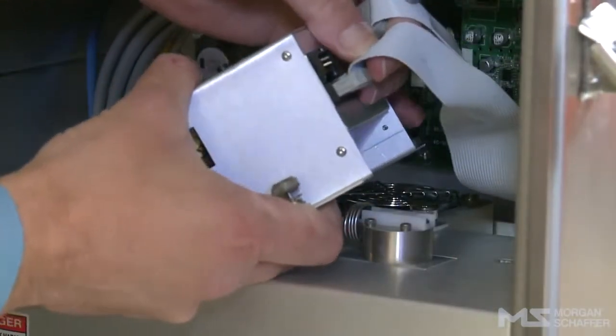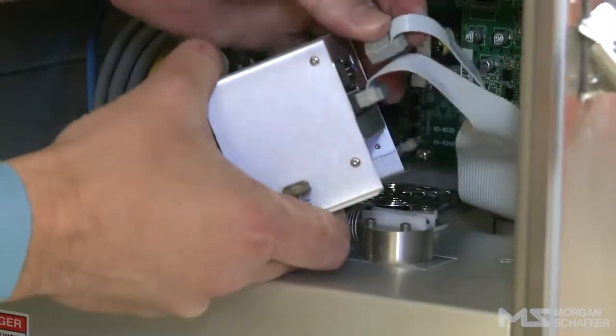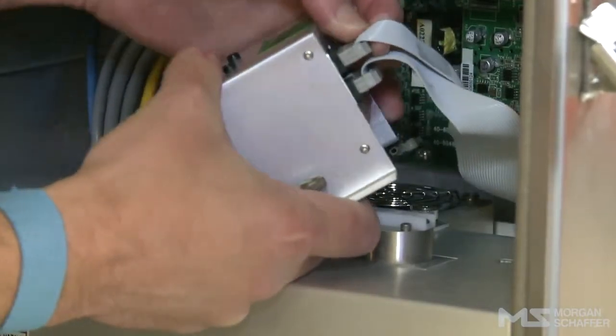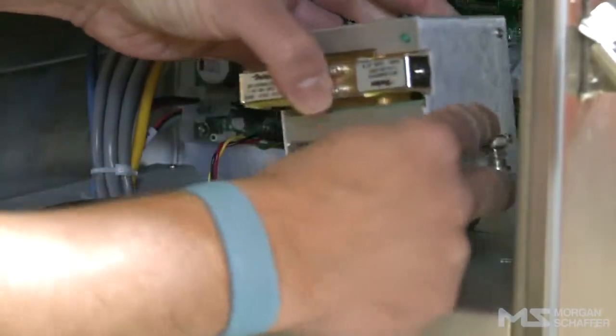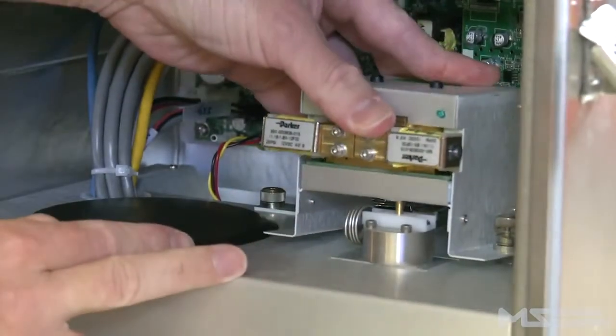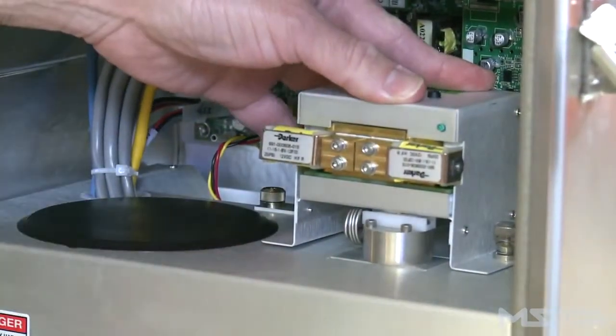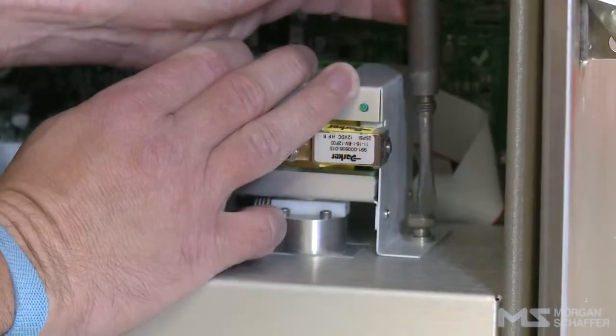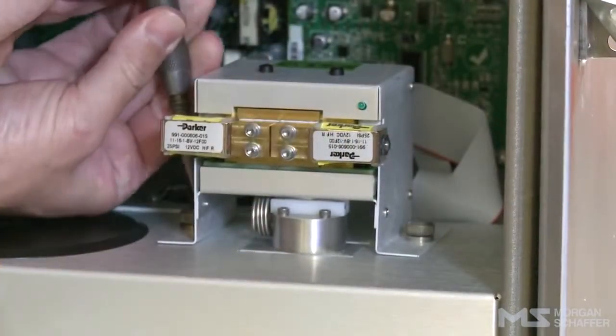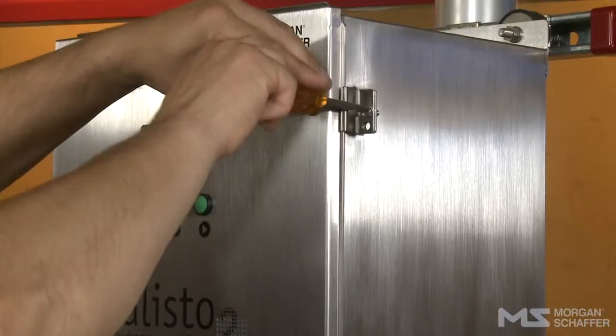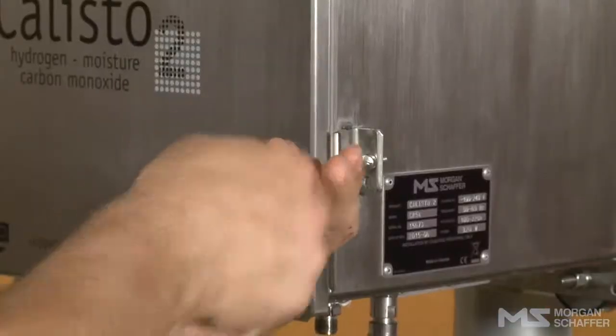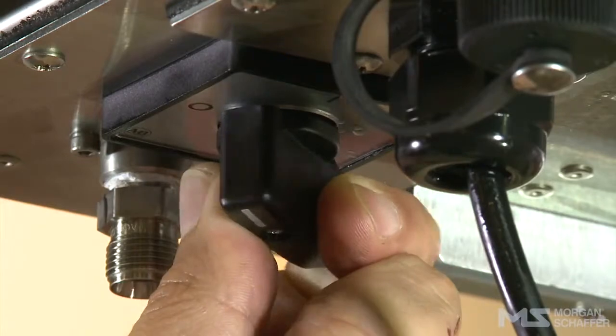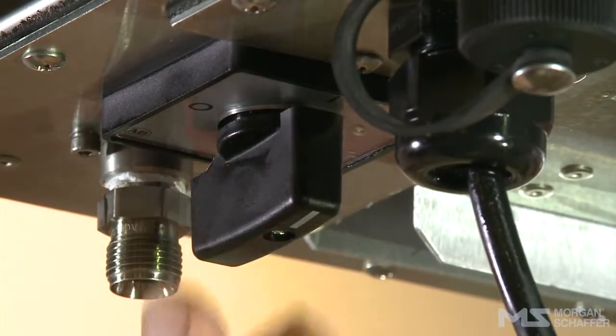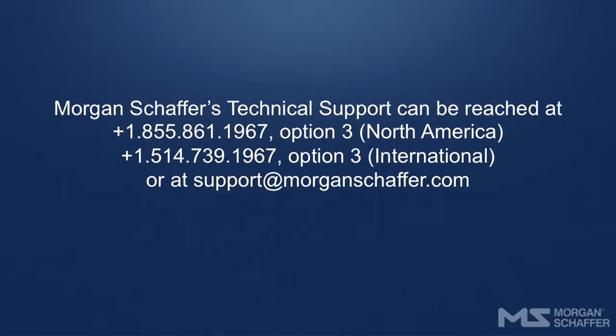Dispose of the old cell and prepare the replacement cell. Reconnect the 2 connectors of the cell's flat cable. Install the new cell by gently inserting the inlet tube in the gas extraction chamber's inlet. Tighten the cell's 2 captive screws to attach the module. Close the door and firmly tighten each of the 2 hinge screws. Restart the Calisto. If the problem persists, please contact Morgan Schaffer for assistance.